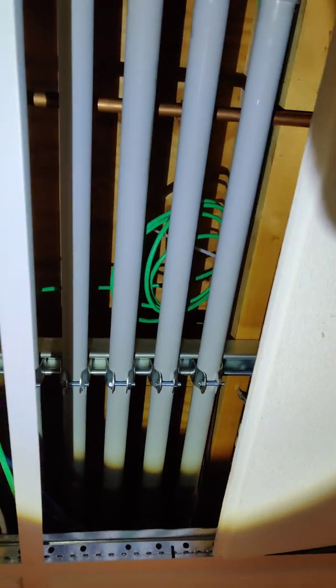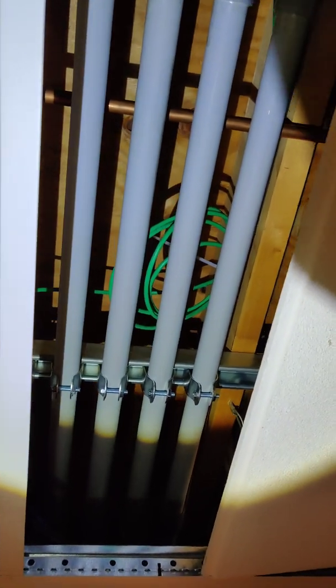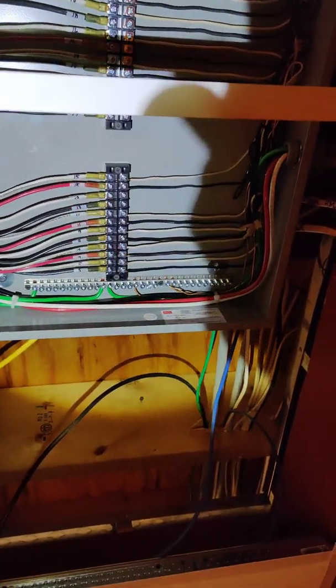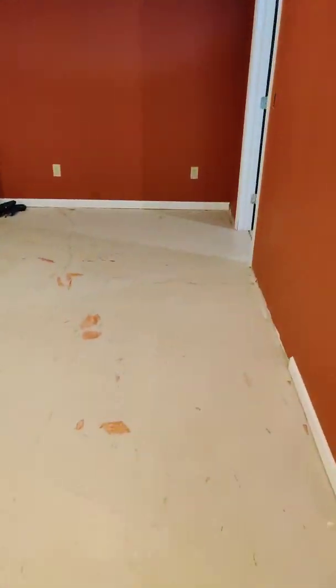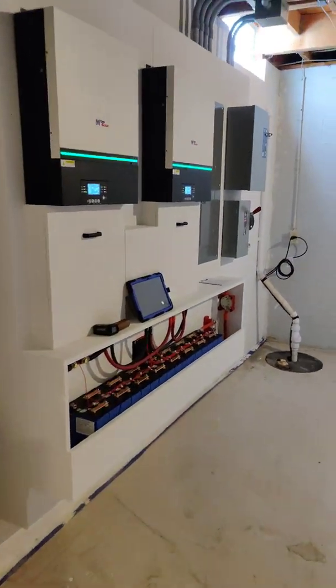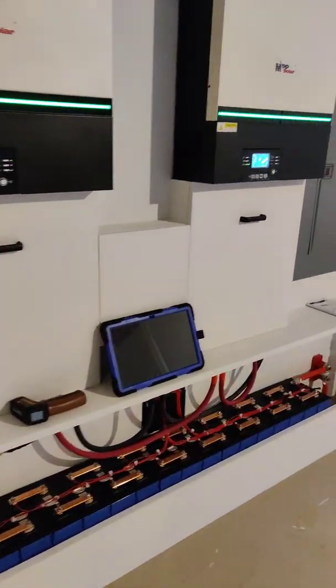It's kind of hard to see here — I've got some of my tiles back in, but I did that because of the derating. Some of you electricians out there know about the derating — with number 10 and a one-inch conduit, you get better fill that way.